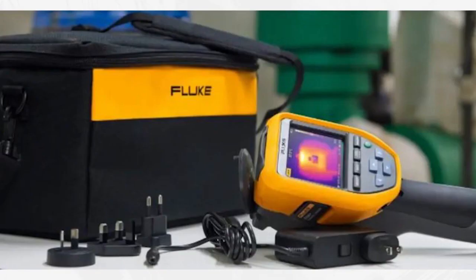We also have thermal imaging cameras that we use, which is a very common diagnostic tool in solar to see if the module is working properly, to see if it's damaged. The interesting thing about solar modules, and this is kind of counterintuitive for most people, is that solar modules actually operate at a lower temperature when they're working properly. Those electrons have somewhere to go when the module is operating. So when the module is not working properly, the electrons don't have anywhere to go, so a certain portion of that energy is being released as heat. So we can see with a thermal camera if that module is hot, then there's usually an indication that it's not operating properly.